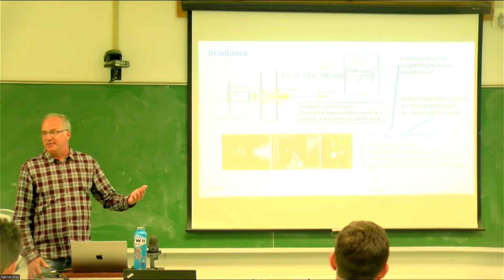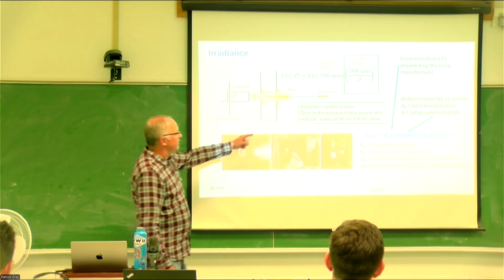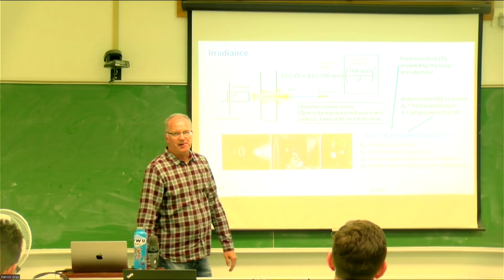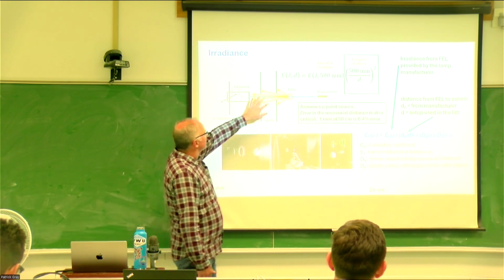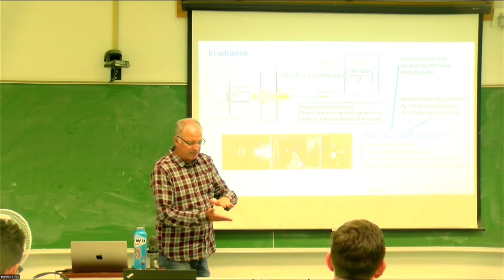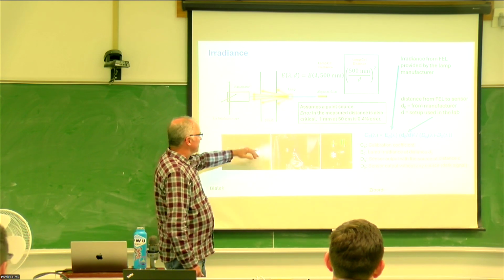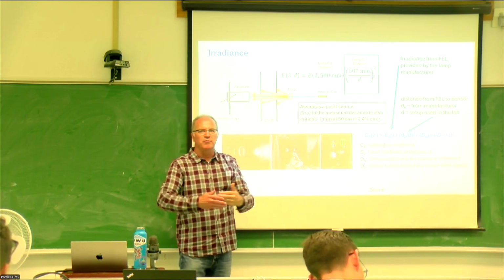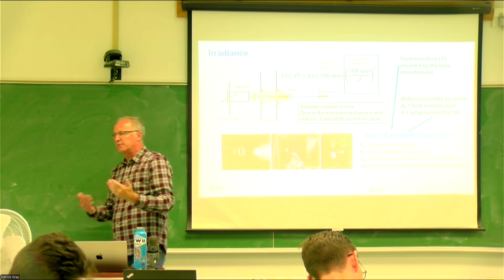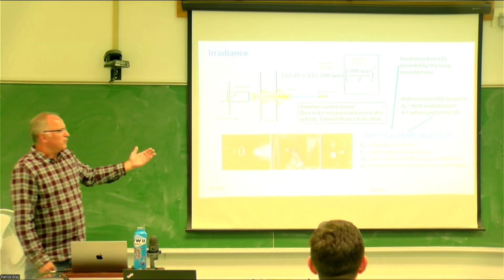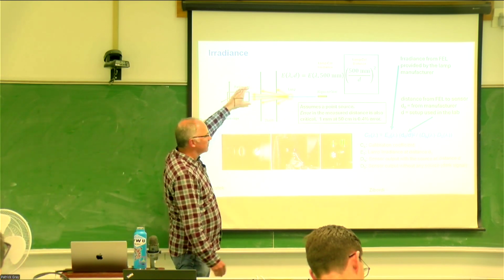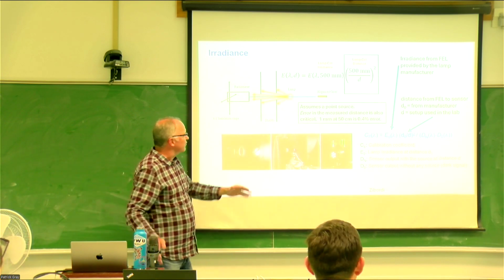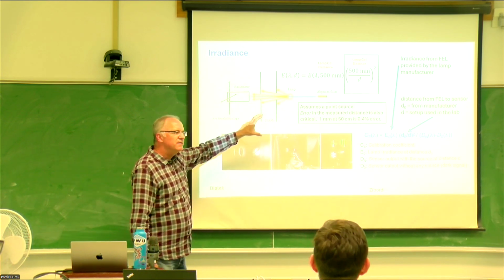And again, the reason for that is we only want to measure one light source. And so these shields are not only baffle systems where I can open up the aperture, but there are also curtain systems here that block one side of the room from the other. Why would we want to do that? We're trying to measure all this light, right? It's coming from a lot of angles. So one question would be, why do you even need these?